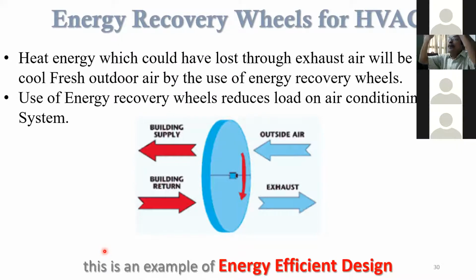When it gets cooled, the moisture which has been absorbed becomes water droplets and comes out as condensate, and the air is again circulated through the room. But one thing not controlled by the air conditioning system is the presence of carbon dioxide. Every time you breathe out, you are giving out carbon dioxide. So all the occupants are breathing out carbon dioxide, and slowly the carbon dioxide level goes up. There is no arrangement inside the air conditioner to get rid of this carbon dioxide.